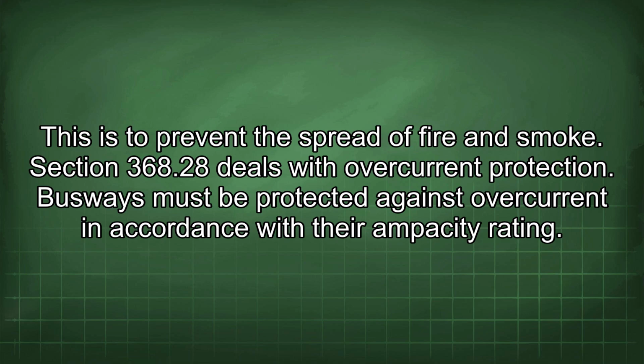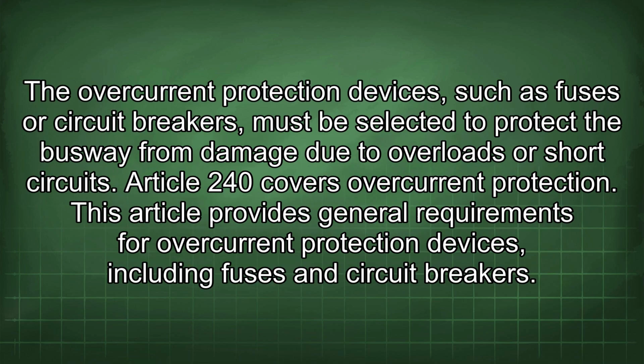Section 368.28 deals with overcurrent protection. Busways must be protected against overcurrent in accordance with their ampacity rating. The overcurrent protection devices, such as fuses or circuit breakers, must be selected to protect the busway from damage due to overloads or short circuits.